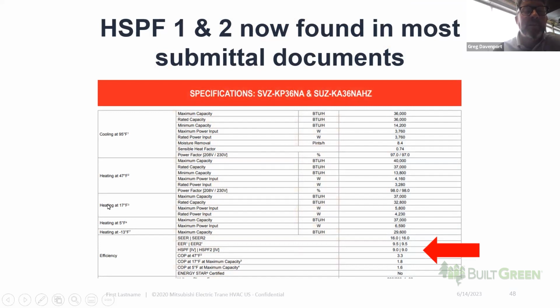This submittal document, if you look down here in the efficiency section, you can see HSPF, and that's for climate zone 4, or HSPF 2, which is the new one for climate zone 4. This is anomalous here, and it may actually be wrong - it's not 9 and 9, it should be something like 9.5 and 9, because with the new HSPF 2 scheme, the numbers are pretty much going slightly down. For all the ducted systems, it's about a 15% reduction. For the ductless systems, it's about a 5% reduction. You'll see an example of that in the next slide here.